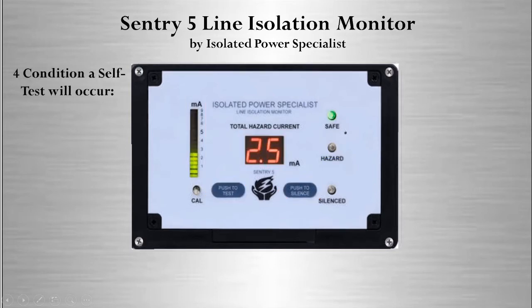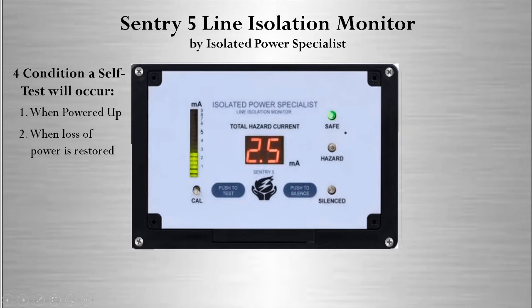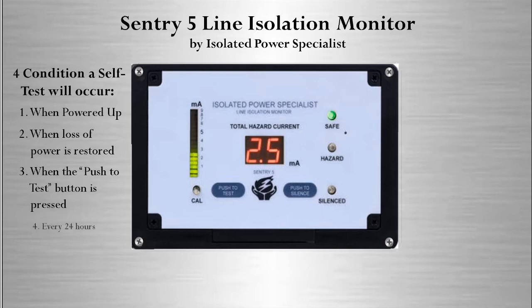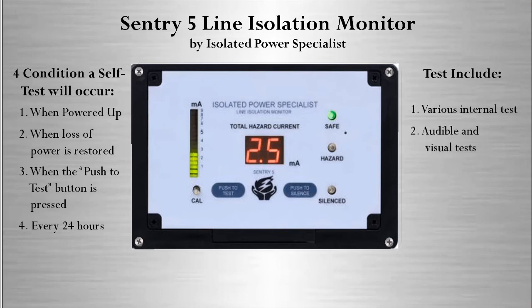There are four conditions under which the Sentry 5 will perform a self-test. One, when it is powered up. Two, if the Sentry 5 loses power then regains it again, it will see this as a power-up situation. Three, you can manually initiate a self-test by simply pressing the push-to-test button. And four, every 24 hours, the Sentry 5 will initiate an internal self-test, but without the audible alarm. The Sentry 5 will perform several internal tests, including the required audible and visual test. Again, the audible test is excluded during the 24-hour self-test.